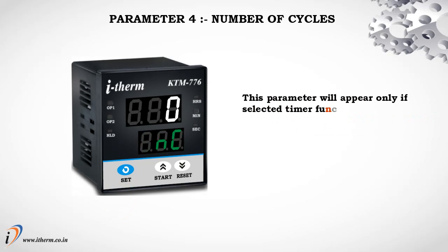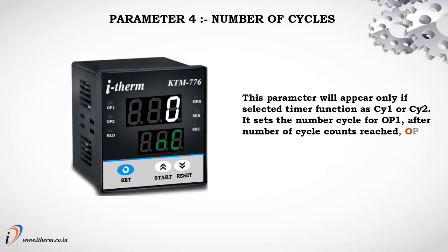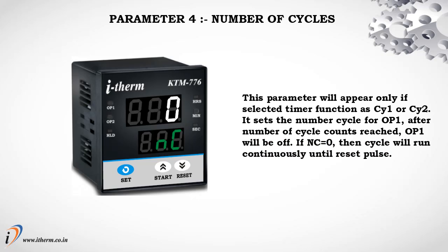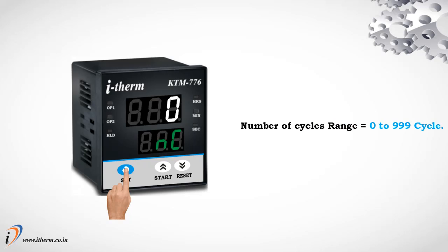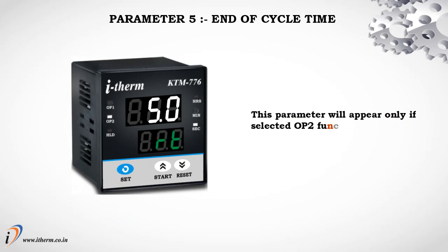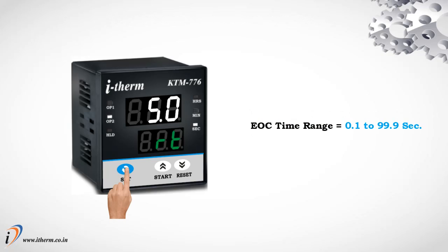Parameter 4: Number of Cycles. This parameter appears only if the timer function is Cycle 1 or Cycle 2. It sets the number of cycles for Output 1. After the count is reached, Output 1 will turn off. If Number of Cycles equals 0, the cycle runs continuously until a reset pulse. Range: 0 to 999 cycles. Parameter 5: End of Cycle Time — appears only if Output 2 function is set to End of Cycle. Range: 0.1 to 99.9 seconds.